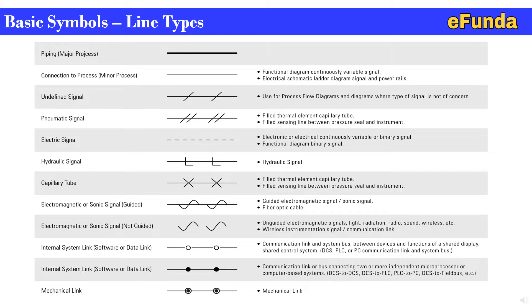A thin dotted line means an electronic or electrical continuously variable or binary signal in functional diagrams. Hydraulic signal is represented by a line through L-sections. The capillary tube — a straight line with two cross signals — represents a filled thermal element capillary tube or filled sensing line between pressure seal and instrument. Electromagnetic or sonic guided signal is a single line with two cross-sectional sinusoidal signatures. Unguided electromagnetic or sonic signal shows only two sinusoidal waves, representing unguided light, radiation, radio, sound, or wireless. Wireless instrumentation signal, communication link, internal system link, software, or data link are also covered.